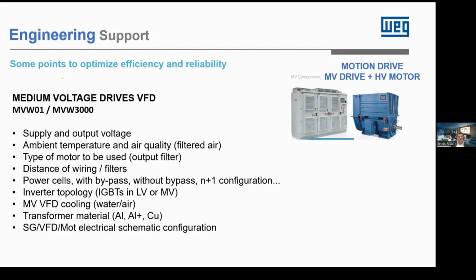Another point that affects efficiency is the material of the input transformer to this drive. Being copper, aluminum, or even improved aluminum, we have different efficiencies and costs, as we were talking about before. But for me, with this holistic idea, the most important thing about this configuration is the motion drive itself, looking at the whole electrical schematic configuration: the medium voltage switchgears that feed the drive, and the drive in turn feeding the motor. By looking at the voltages and the powers, we can optimize the investment prices and the efficiencies of each of these parts, so that together they give the highest efficiency and the best possible cost. This is the reason I was talking before about this holistic idea and supporting the engineering from the beginning.